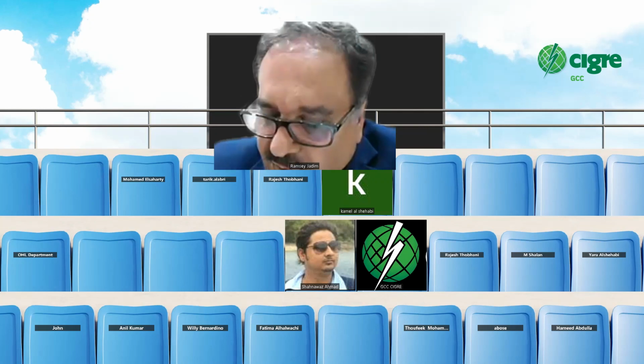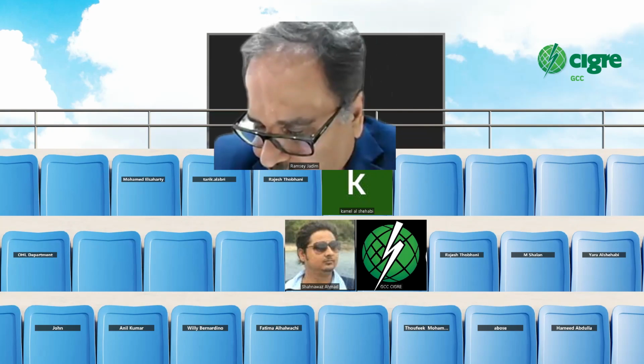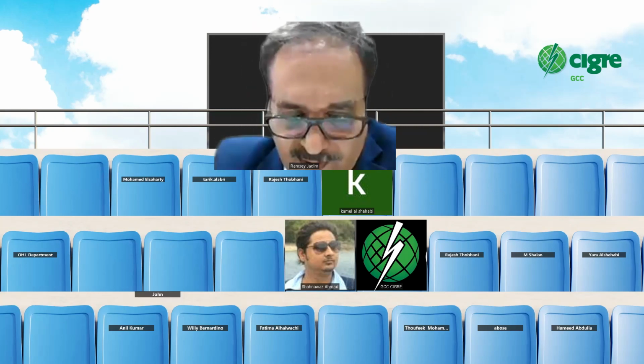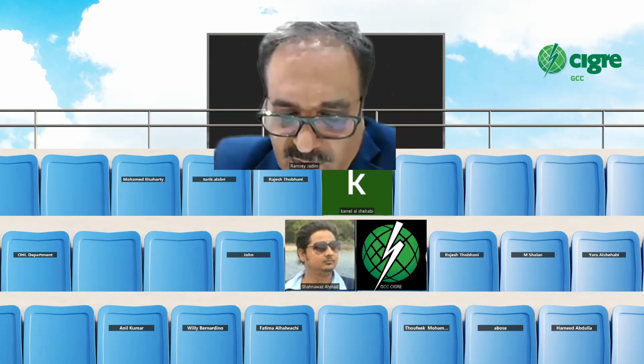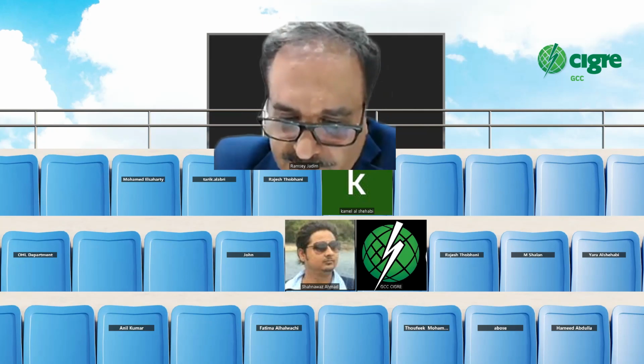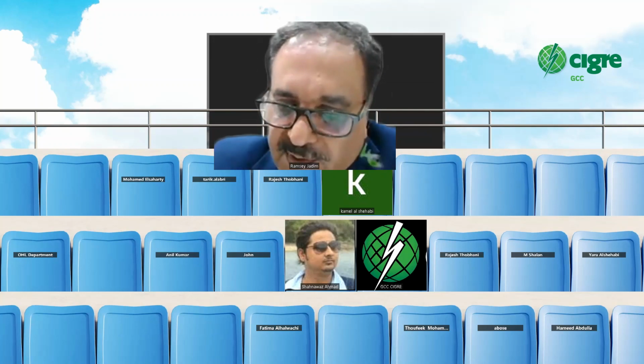Yeah, this is very good information of the gases, right? Yes, from the trend of gases. Yeah, from the trend. So therefore, Mr. Tariq, we need to do it frequently, this one, to see if it is increased or not. Clear. Thank you, Doctor. Thank you, Ragesh. Welcome. And the increase should be not more than 10% per month.